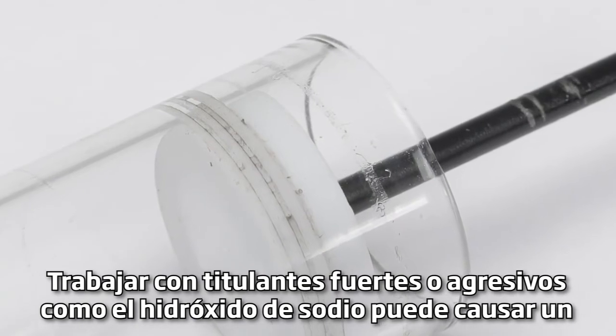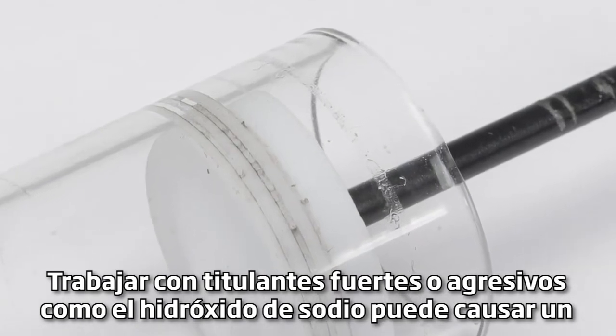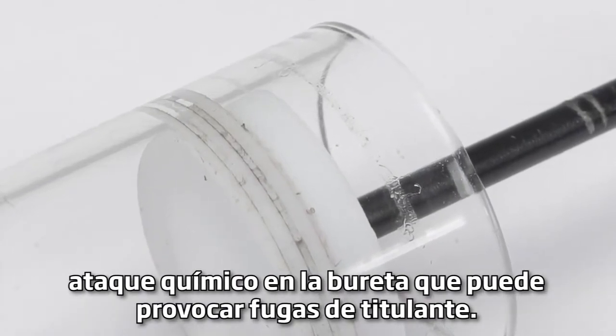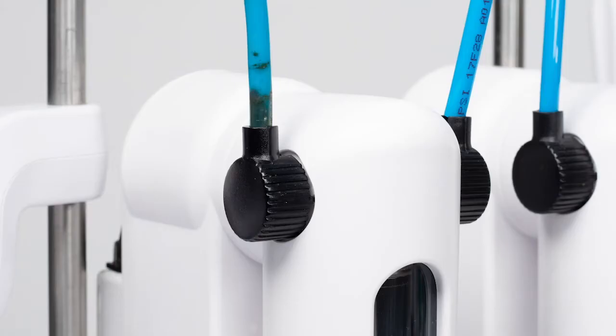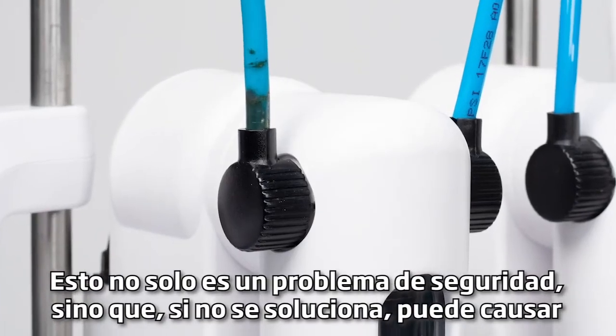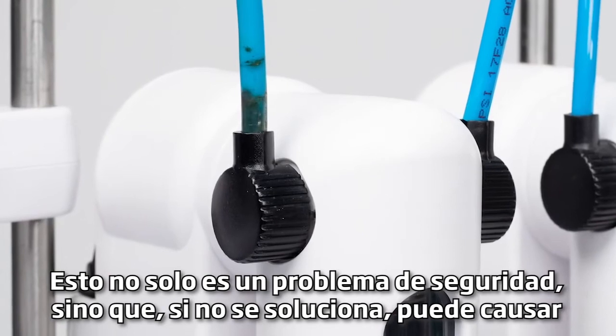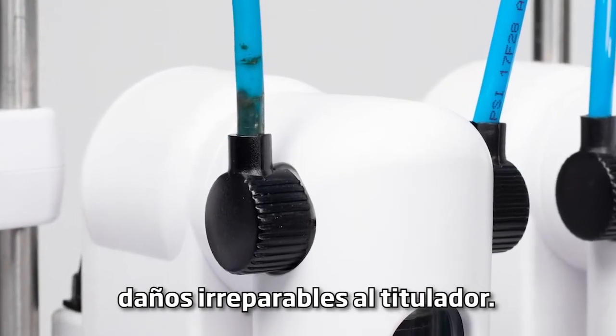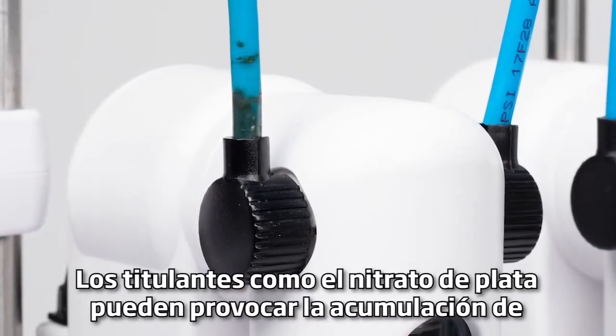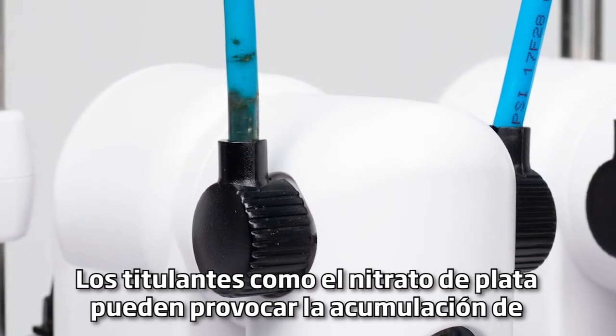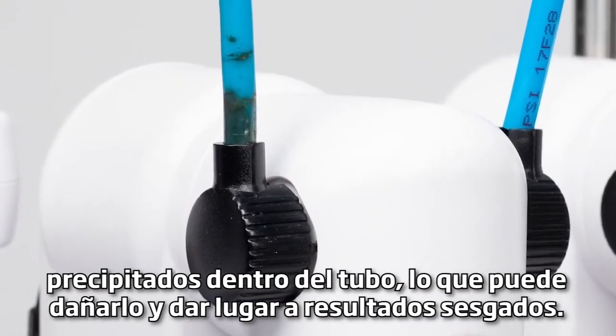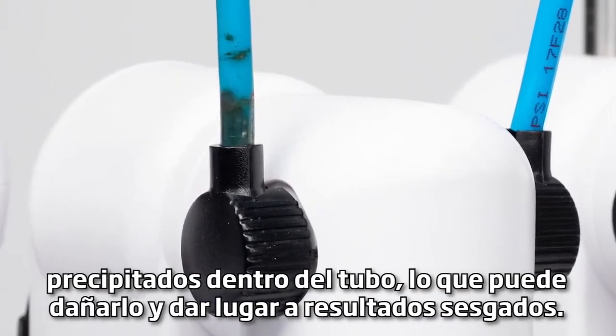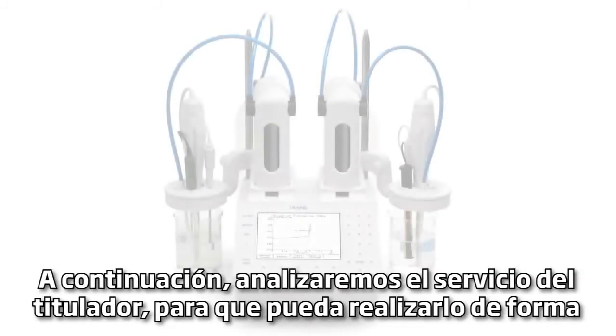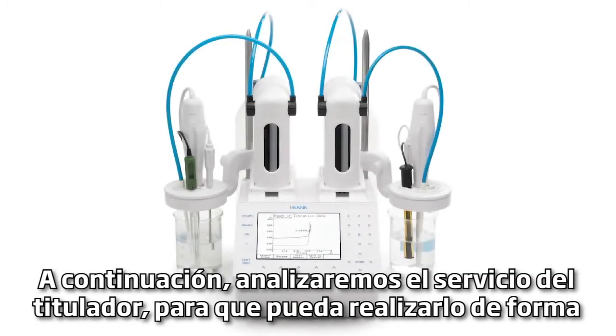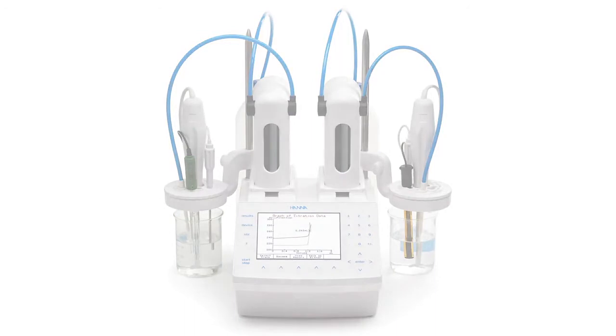Working with strong or aggressive titrants, like sodium hydroxide, can cause etching on the buret, which can lead to titrant leakage. Not only is this a safety concern, but if left unfixed, it can cause irreparable damage to the titrator. Titrants like silver nitrate can cause precipitate buildup inside the tubing, which can cause damage to the tubing and lead to skewed results. We will now walk through servicing the titrator, so that you are able to perform this independently.